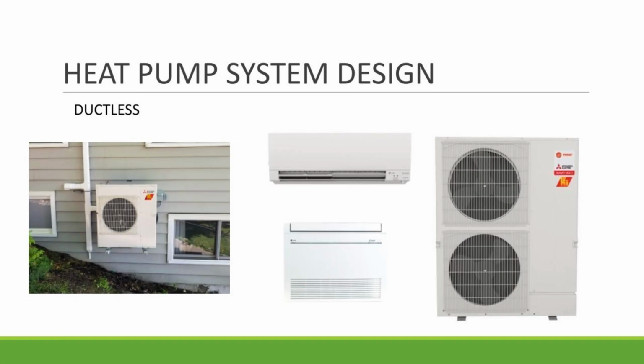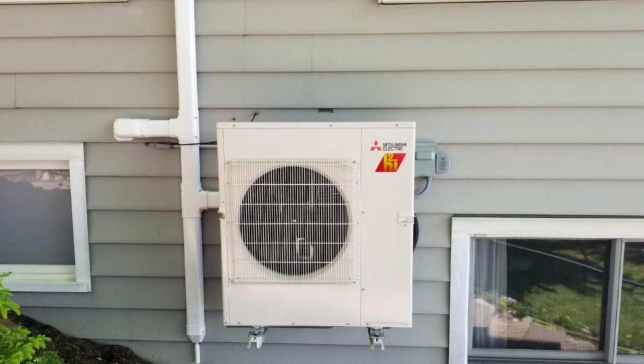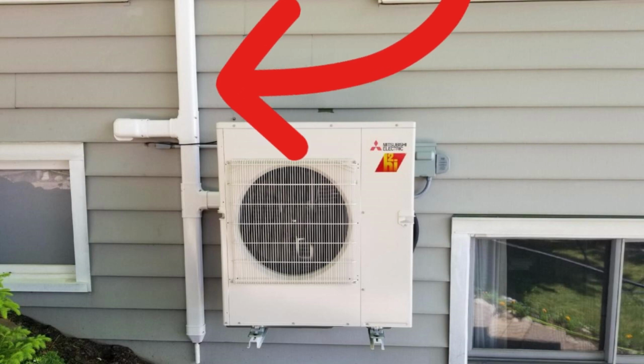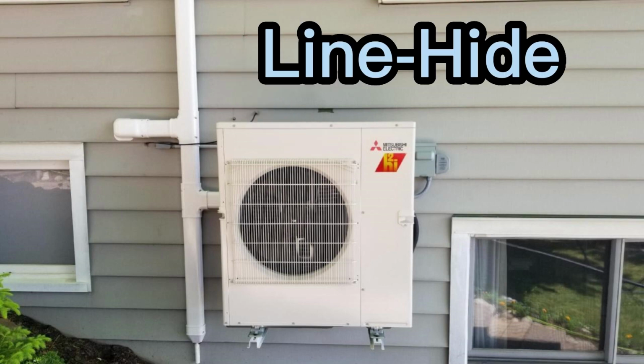Typically, what we would see is what's considered a ductless system. This is where we would have individual head units inside of the house, usually on a high wall somewhere. There would be an outdoor heat pump that would be mounted to the house or possibly stand mounted. You would see the refrigerant lines run on the outside of the house. Those typically get covered with a product called line hide. It's just an enclosure. This can be done in a multi-zone system or a single head system. In a multi-zone application, you'd have multiple indoor head units that all route to one outdoor unit.